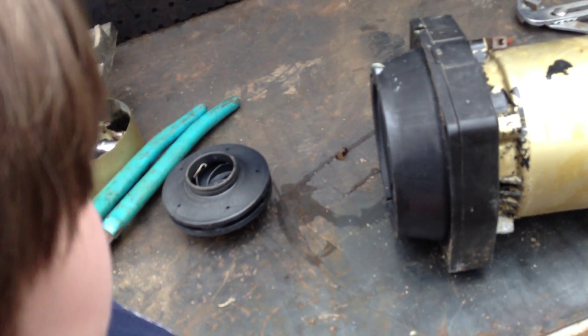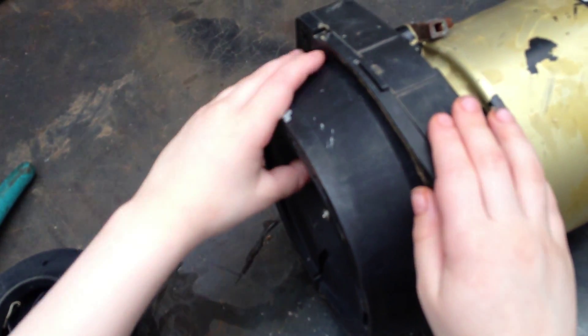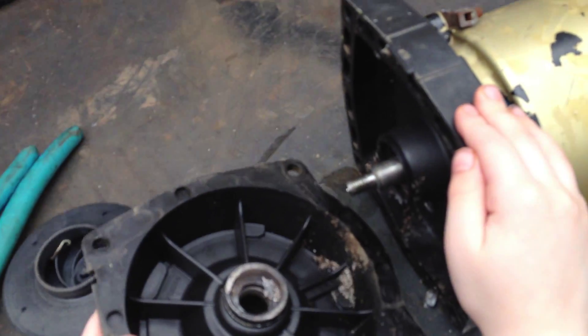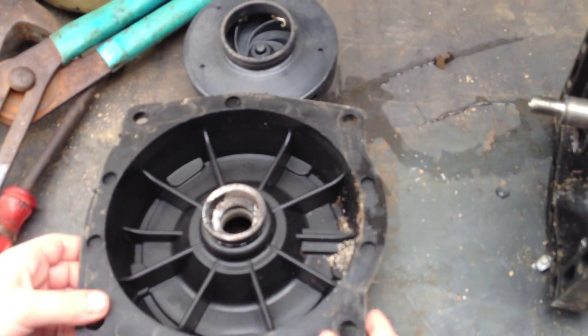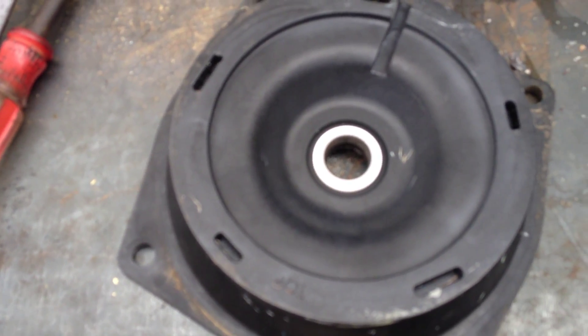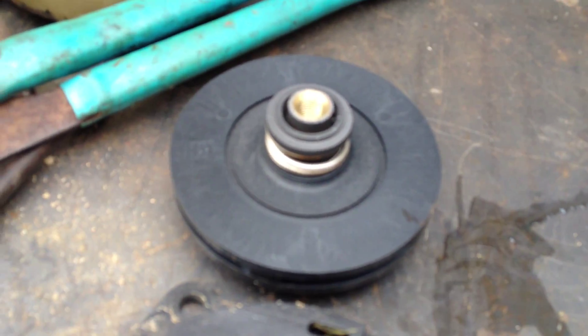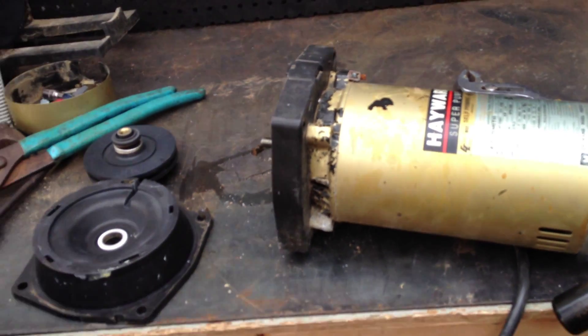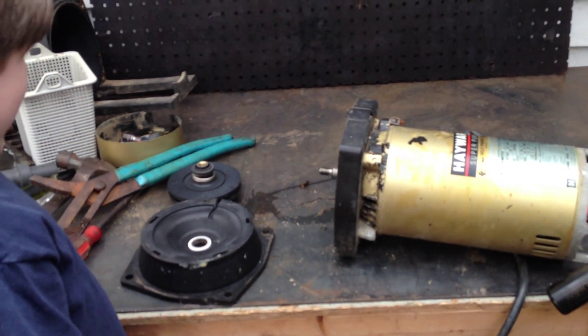After you remove that impeller just like that, go ahead and show them how to remove the seal housing. The seal housing is going to just shake and you'll see it will just separate just like that. Now flip that over and you'll see — that white section there is one part of the seal housing. And if you flip the impeller over, that is the other part of the seal. Our kits include both of these parts — the white section, the spring section, and the motor bearings. All parts are available at wetheadpumprepair.com.